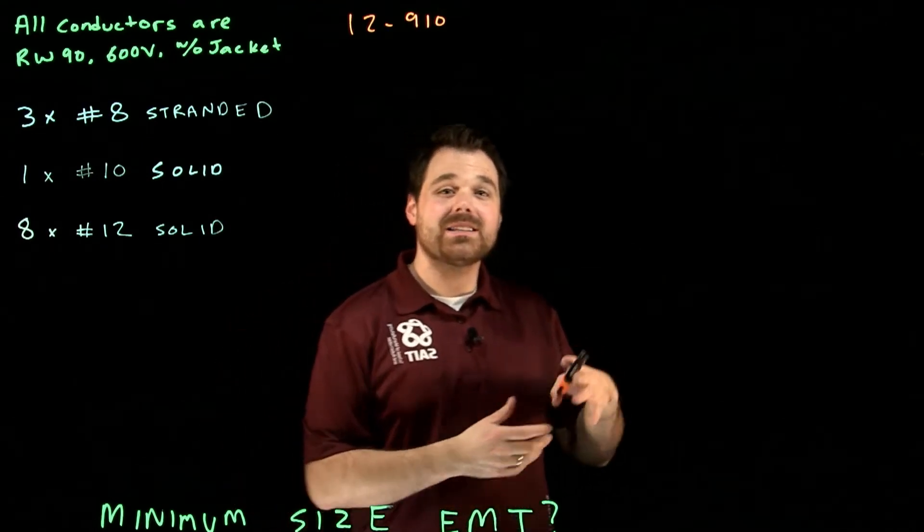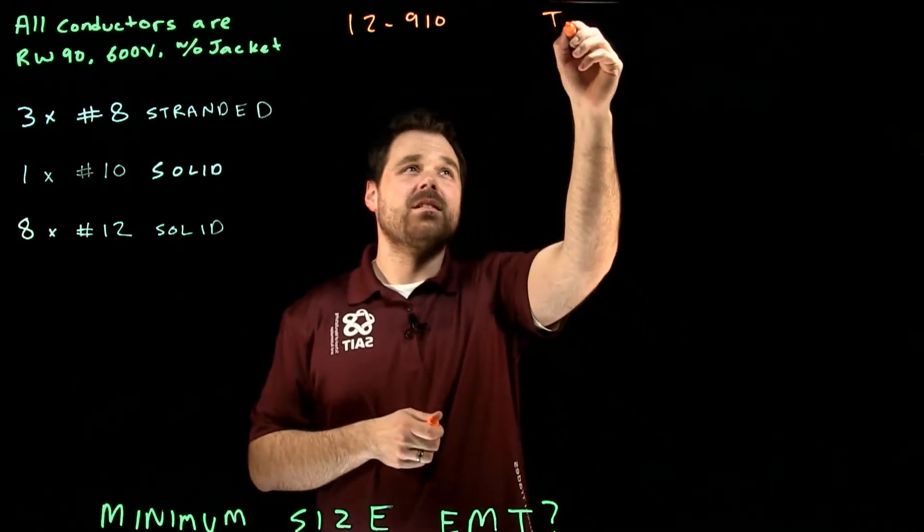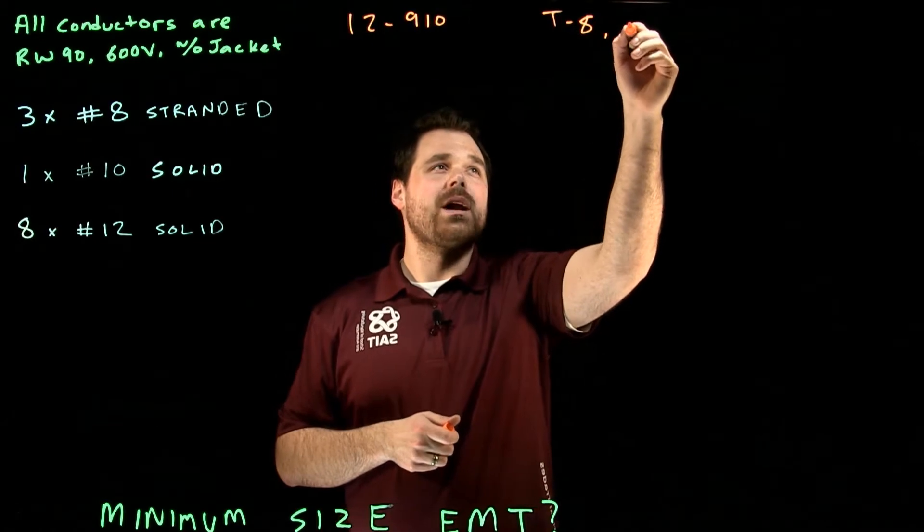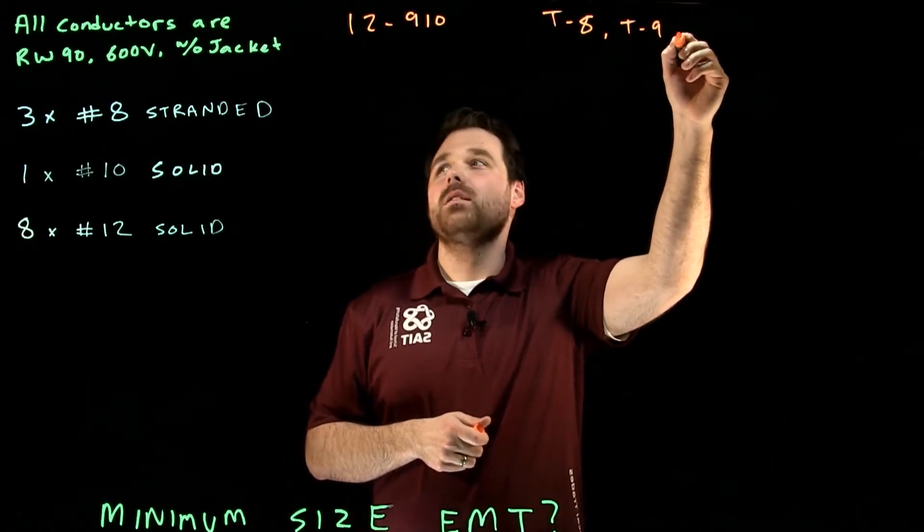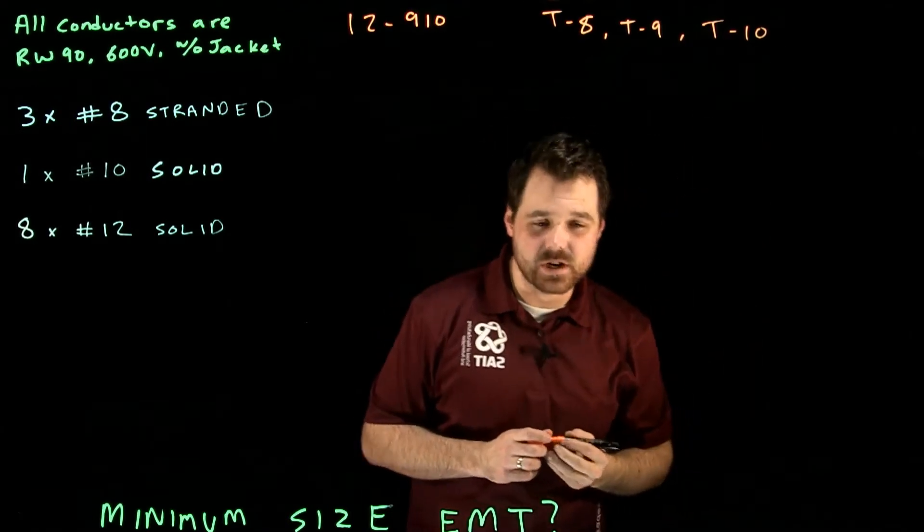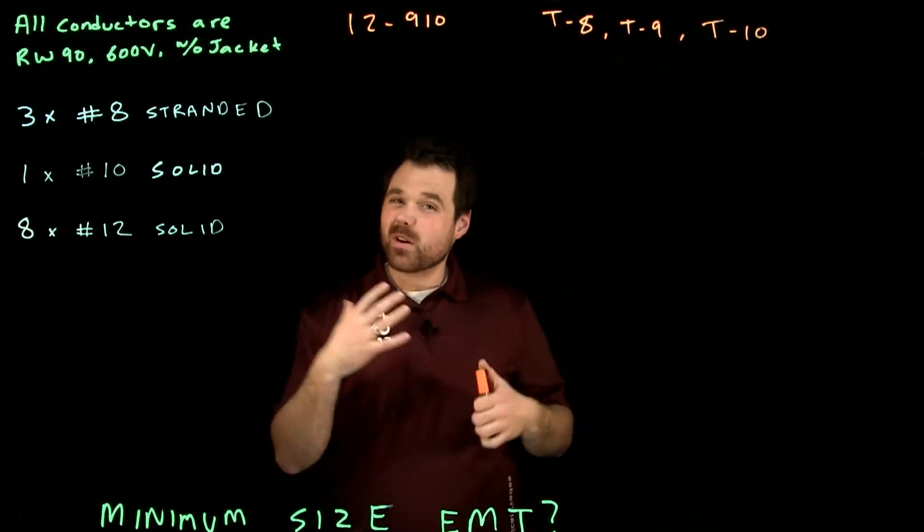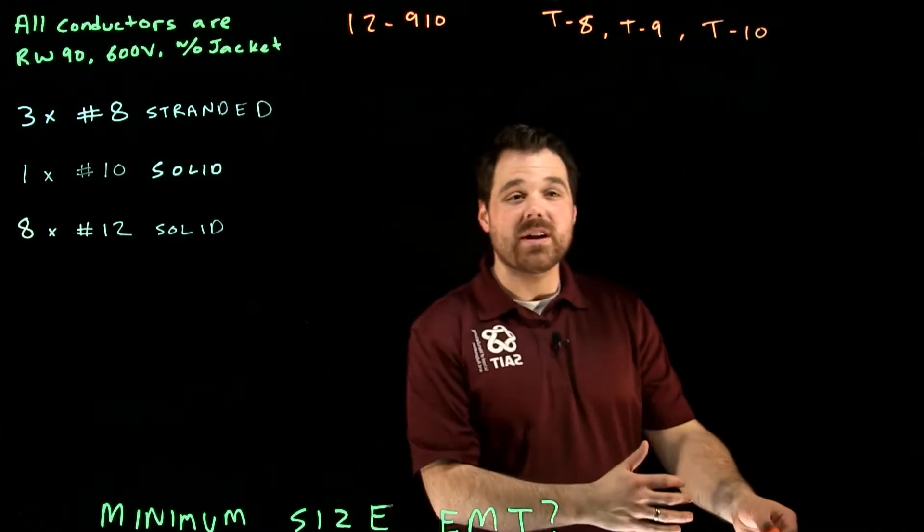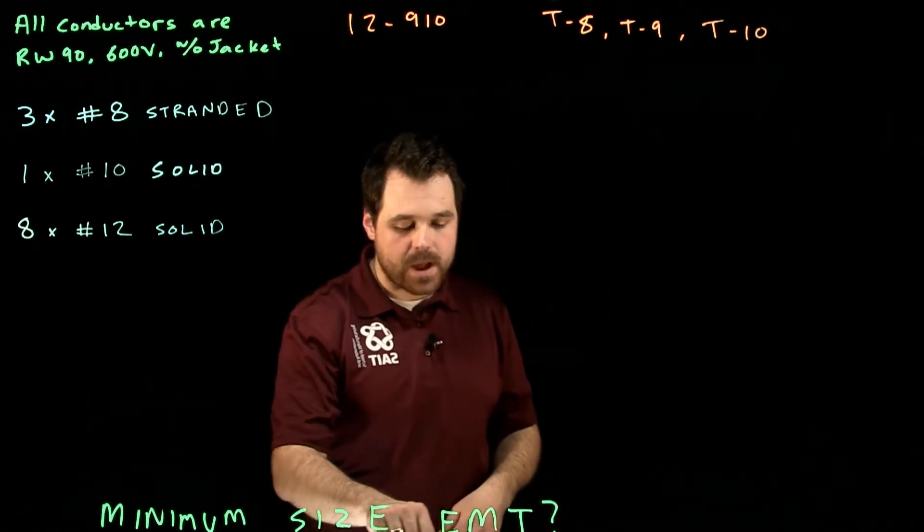We're going to have to use tables 8, 9, and table 10 to size these conductors. Keeping in mind, if they all were the same size conductor, we could just go right to table 6, A through K and size it based on that.